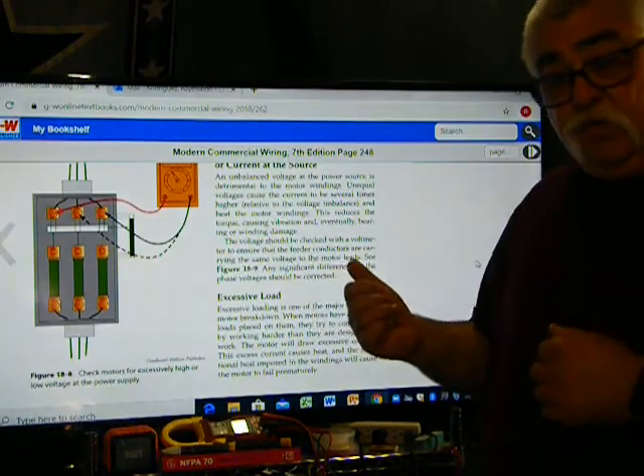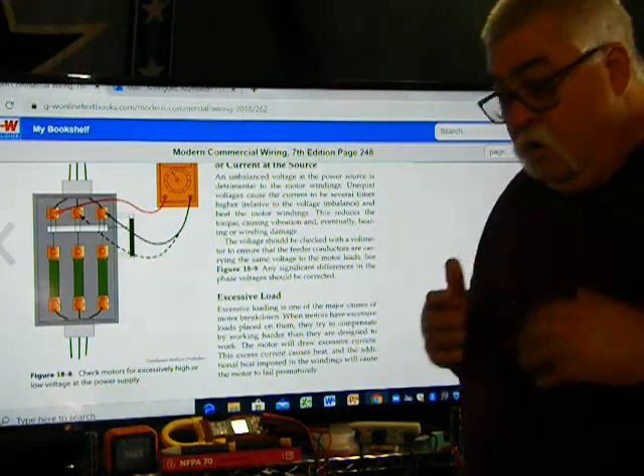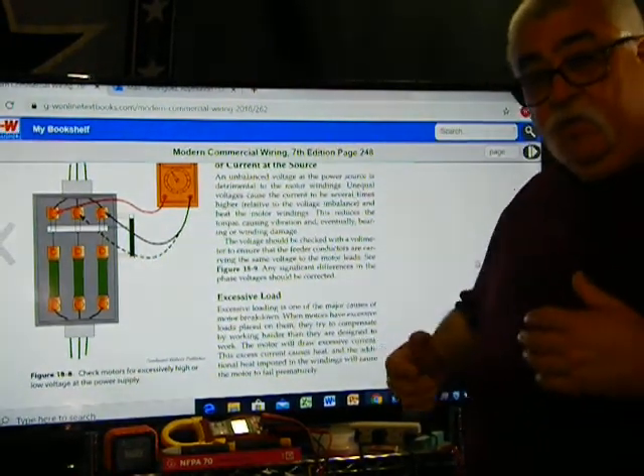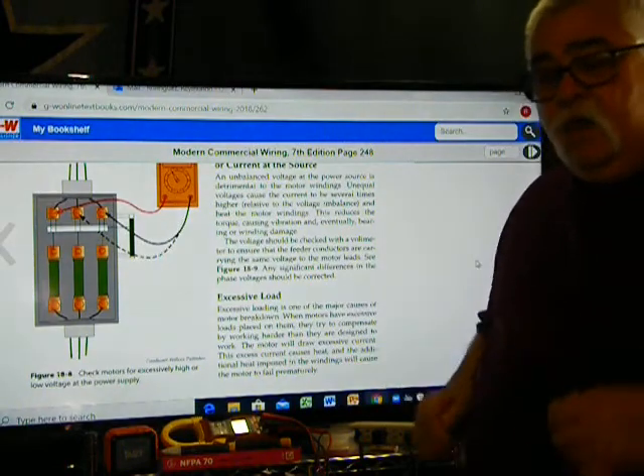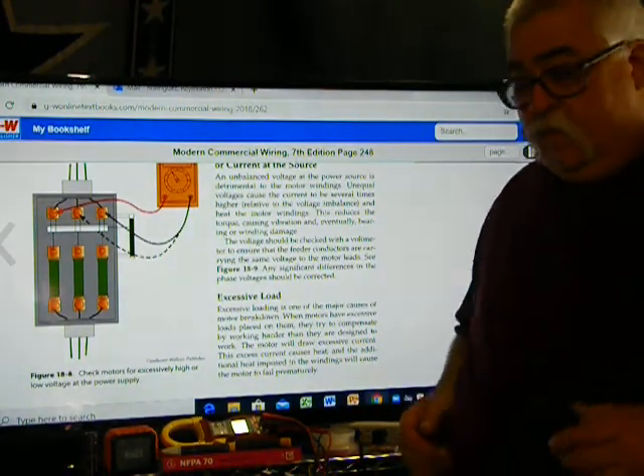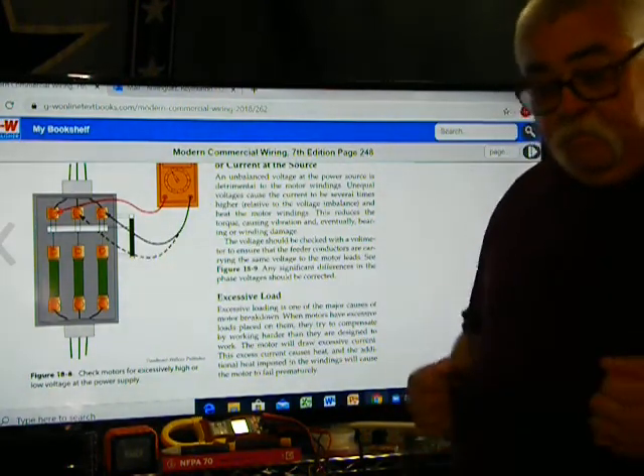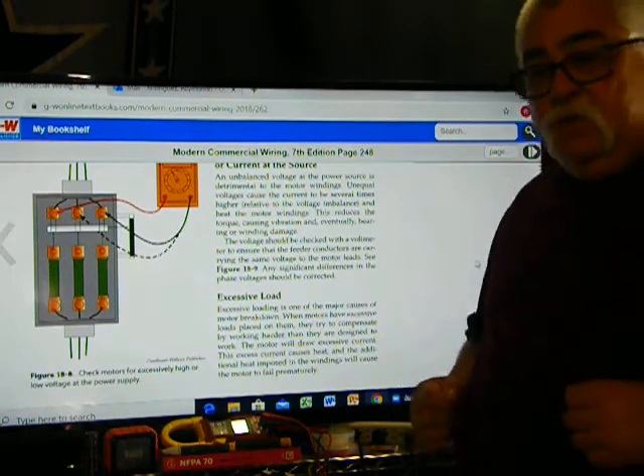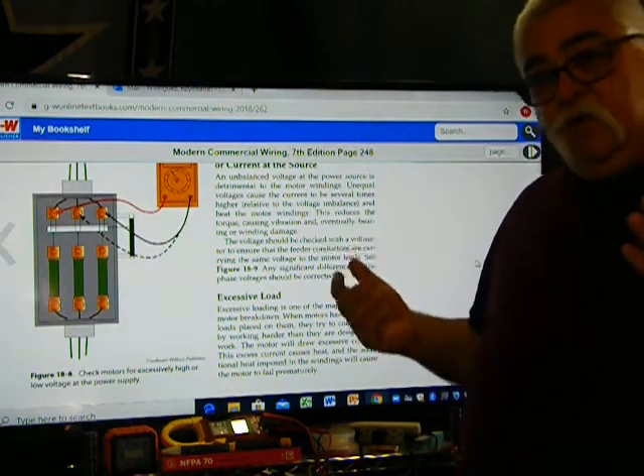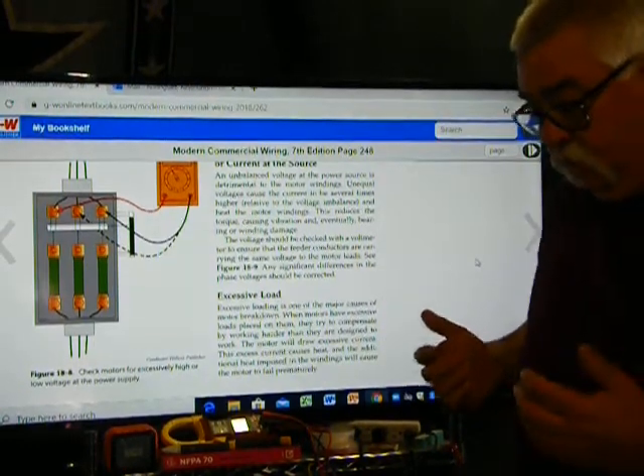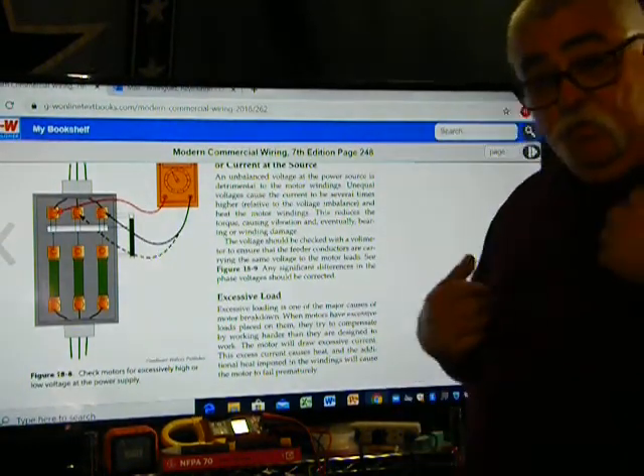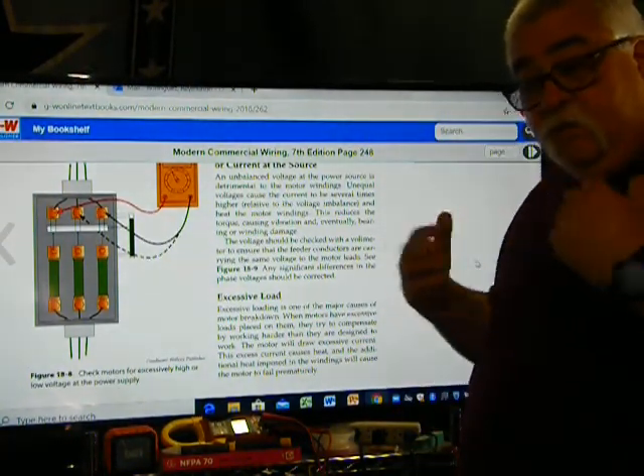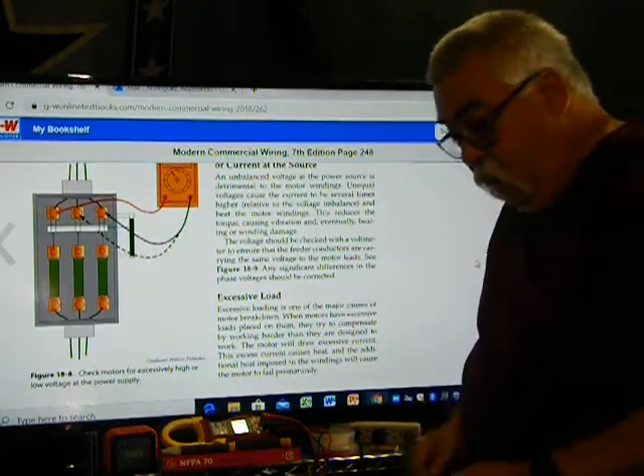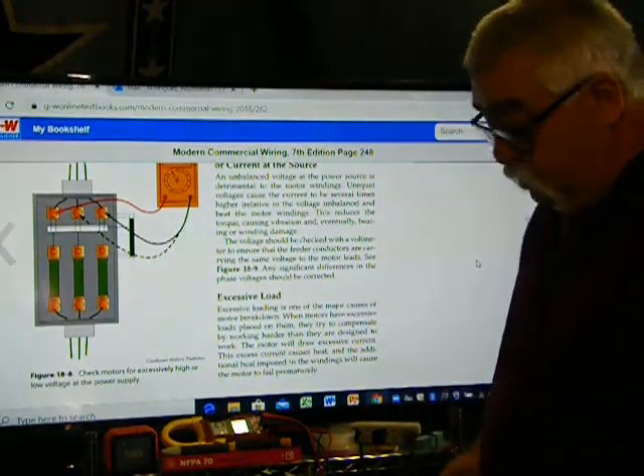Voltage unbalance creates more heat. It's trying to work harder, and it's like if you're working calm and you're okay, you're cool, and then all of a sudden you have to put some pump into it, what happens? You start to get hot, so you have to be very careful. Just like when you're working outdoors, you have to keep yourself cool so you don't overheat. Same thing with these motors.